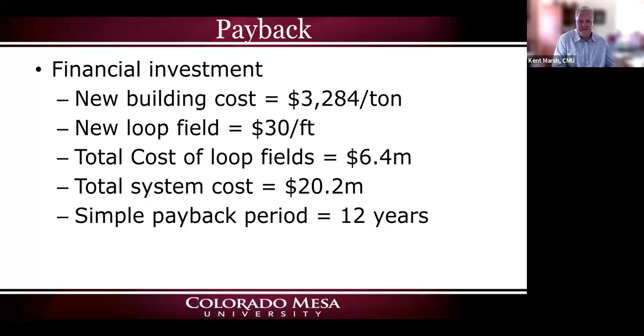Our system is no exception. Our total cost for drill fields, back when I did this calculation, was about $6.4 million. Our total cost, including all the pumps and the central loop system, was about $20 million. We were saving about $1.5 to $1.6 million a year, which gives a payback of just over 12 years. The lion's share of our system is large and small pieces of high-density polyethylene pipe, which will be in the ground forever.